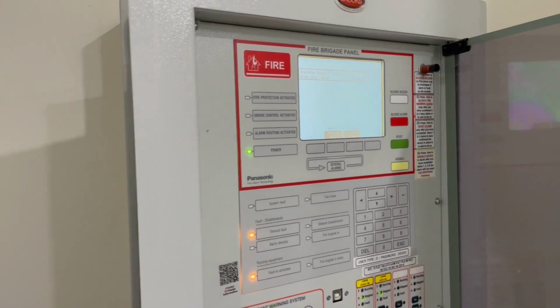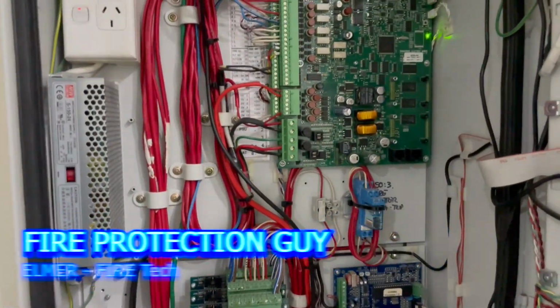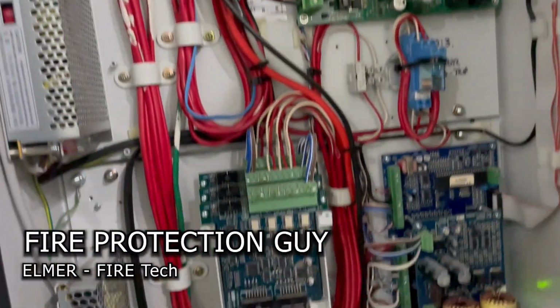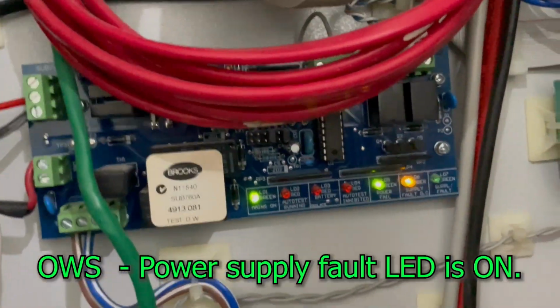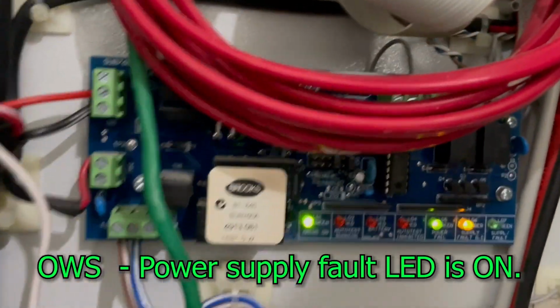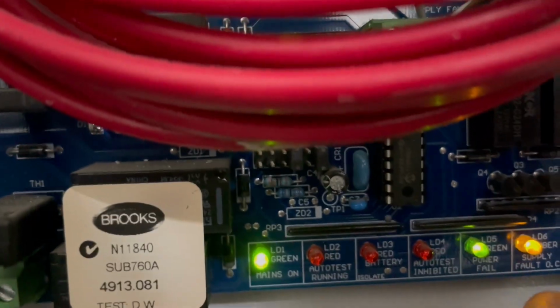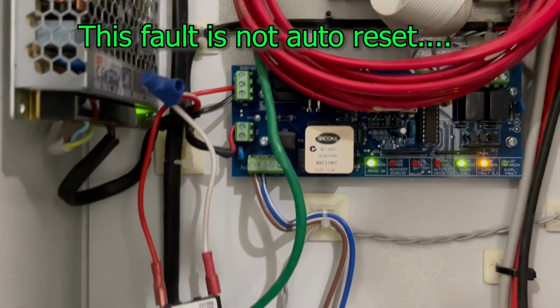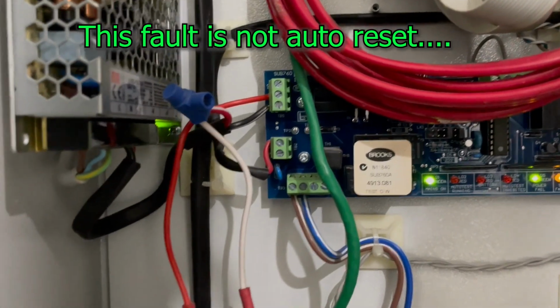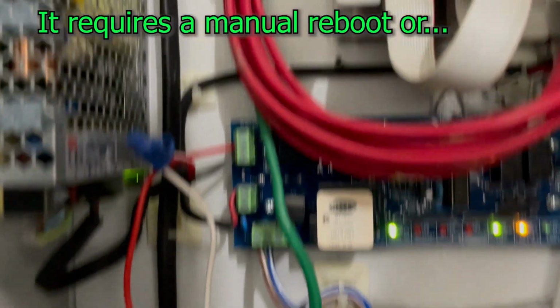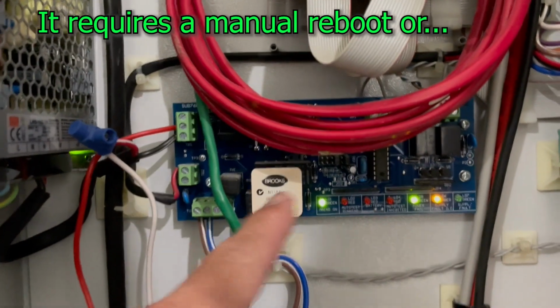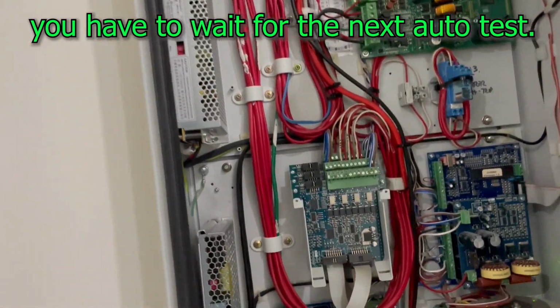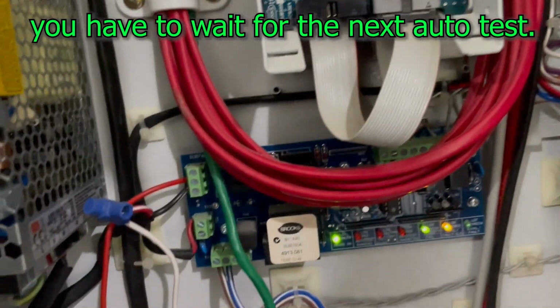Okay, we're going to open up the panel. That's the G3 fire panel. And there's your occupant warning system. And you have a fault. The fault is a supply fault. What I normally do here, it happened before. See the switch? I installed this so I can switch off that particular occupant warning system without switching off the whole system. That's why I did this.